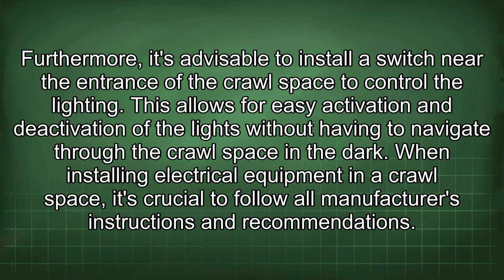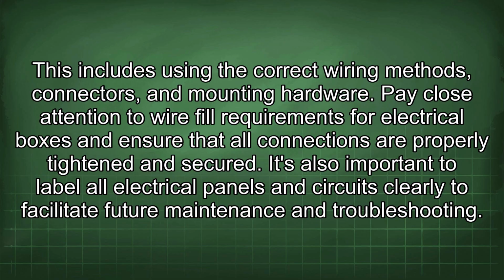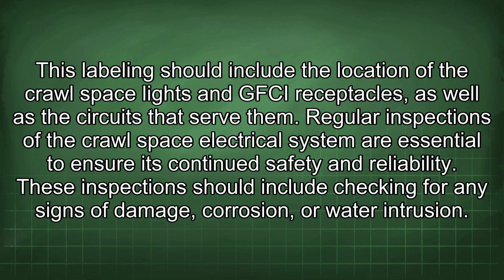Furthermore, it's advisable to install a switch near the entrance of the crawl space to control the lighting. This allows for easy activation and deactivation of the lights without having to navigate through the crawl space in the dark. When installing electrical equipment in a crawl space, it's crucial to follow all manufacturers' instructions and recommendations. This includes using the correct wiring methods, connectors, and mounting hardware. Pay close attention to wire fill requirements for electrical boxes and ensure that all connections are properly tightened and secured. It's also important to label all electrical panels and circuits clearly to facilitate future maintenance and troubleshooting. This labeling should include the location of the crawl space lights and GFCI receptacles, as well as the circuits that serve them.